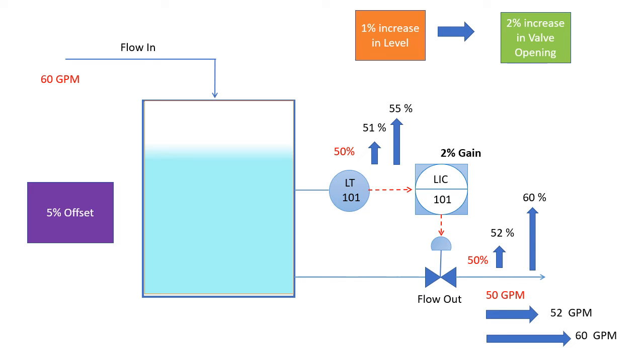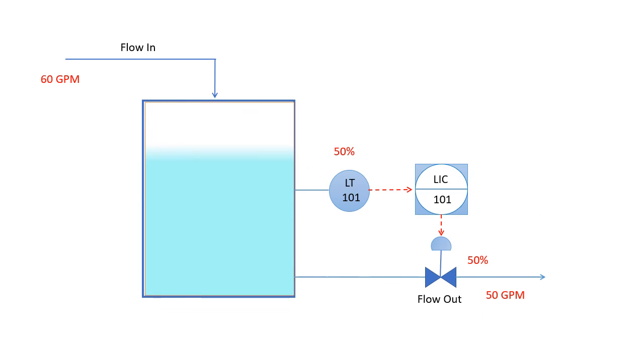One of the easiest ways is to increase the gain. Suppose you increase the gain to 5 percent. Now for 1 percent increase in level will cause 5 percent increase in valve opening.